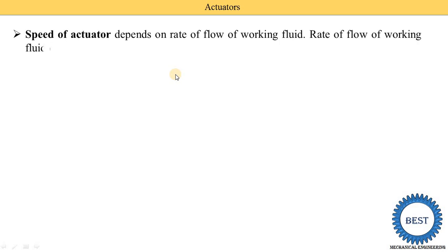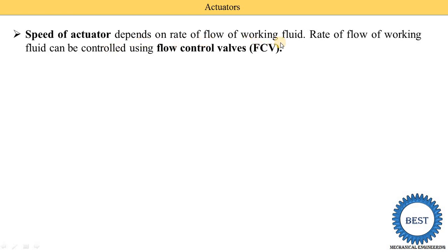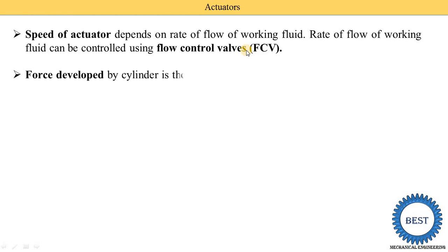The speed of the actuators depends on the rate of flow of the working fluid. Speed depends on the quantity of working fluid supplied, i.e., the flow rate Q. The rate of flow of the working fluid can be controlled by using flow control valves, abbreviated as FCV. By using the FCV, we are able to control the speed of the actuators.